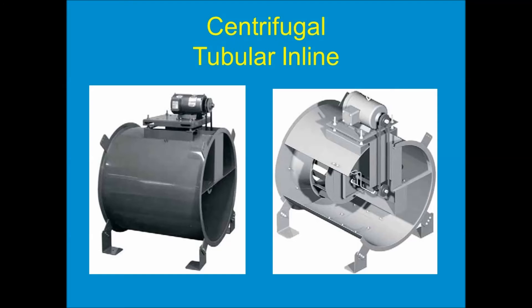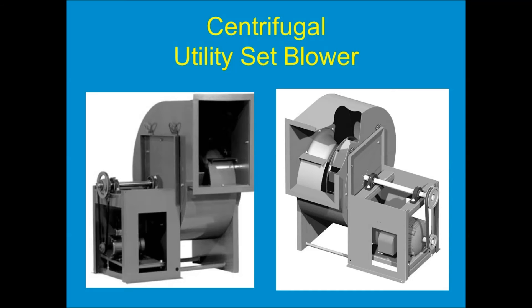We take that centrifugal impeller mounted in a welded tube and we have a tubular inline fan. This fan can only move air in an inline direction — we can't turn the air 90 degrees off the side of a welded tubular housing. The centrifugal impeller is what's used for utility ventilators and blowers — very common workhorse fans that can move a lot of air against a lot of pressure, and sometimes most importantly, a little bit of air against a lot of pressure. A blower type fan like this is very versatile — we use these almost exclusively in vehicle exhaust applications where we might only need to move six or seven hundred CFM but against five, six, seven, or eight inches of pressure, because of the high velocity small diameter ductwork used.